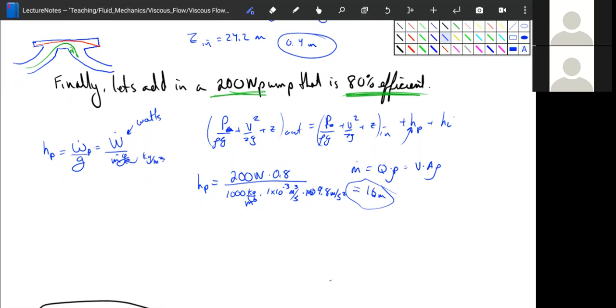And if we plug that into here, remember all these pressures cancel out, Z out cancels out. We're solving for Zn. We know our V out, our Vn cancels out actually. We know our head losses. We've already calculated those up above. We find out that our new Zn is equal to 8.2 meters, which is still, frankly, ridiculous. 24 feet tall tank. You never see those except in some extreme situations.